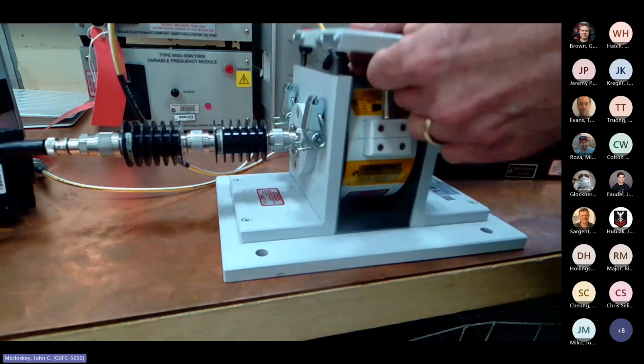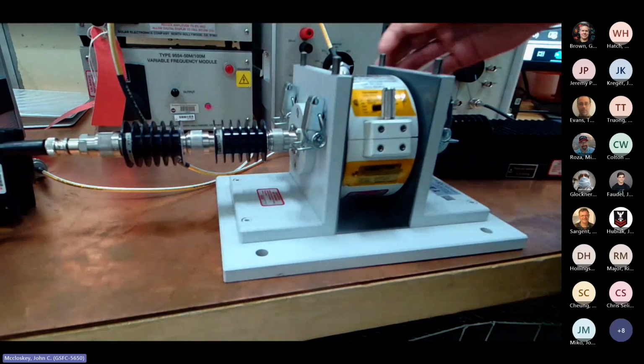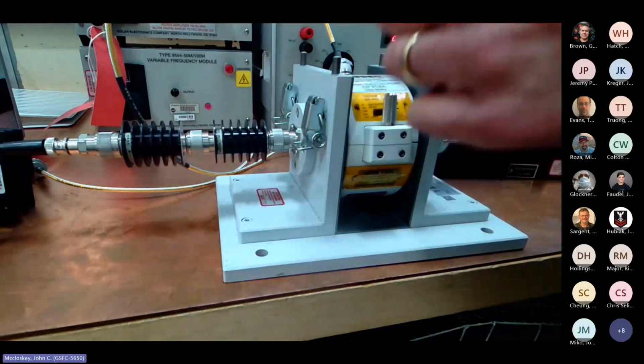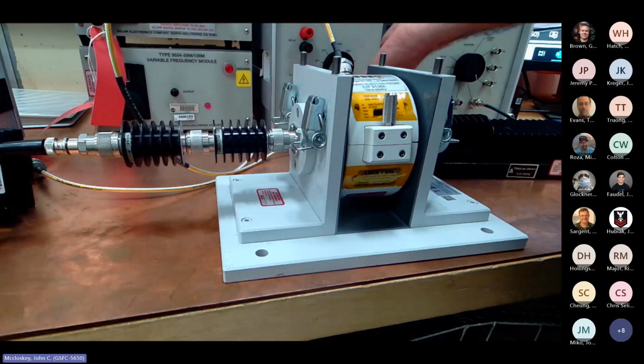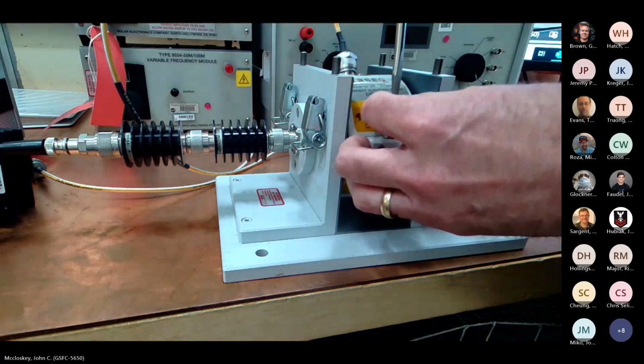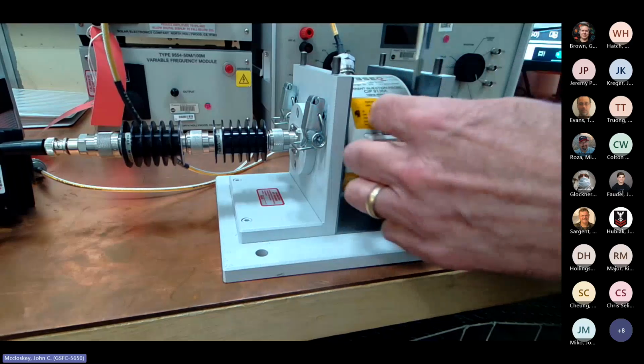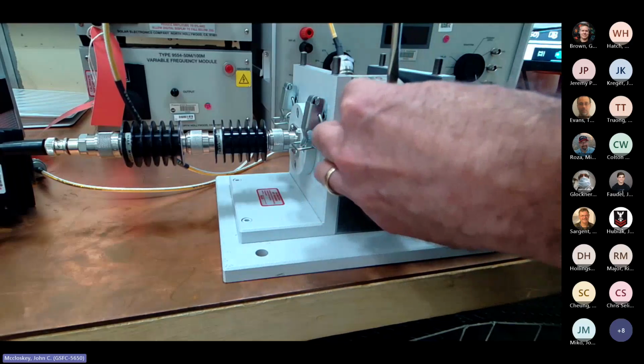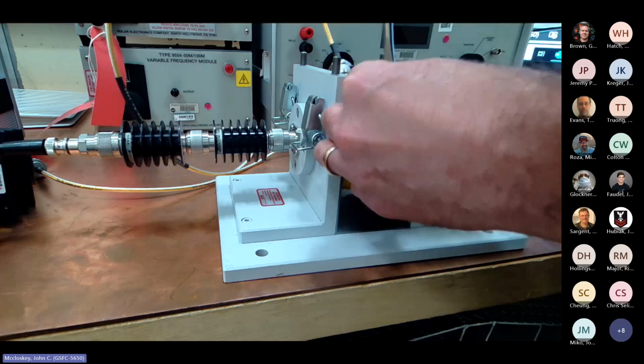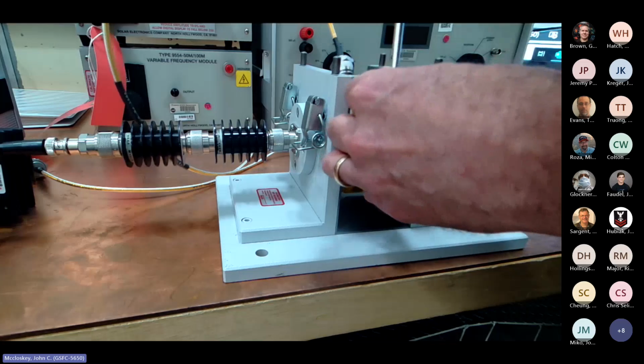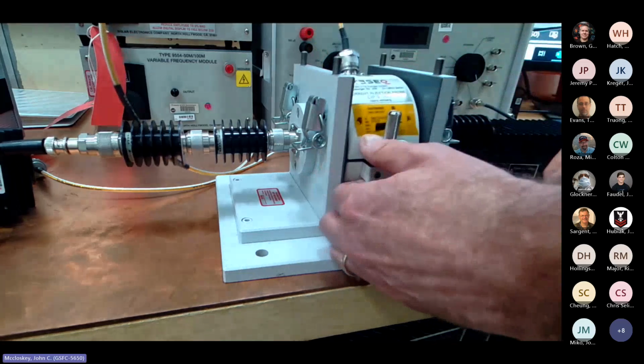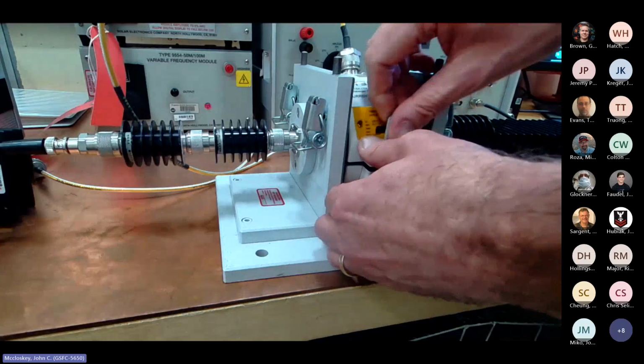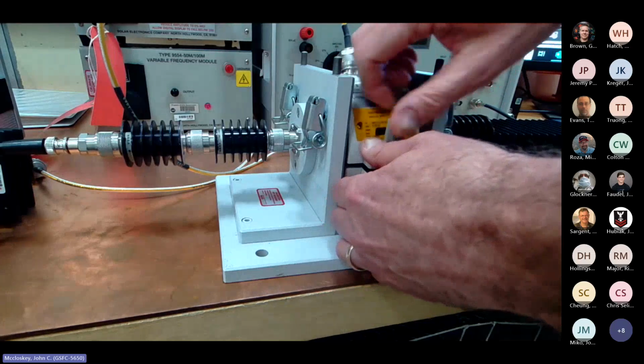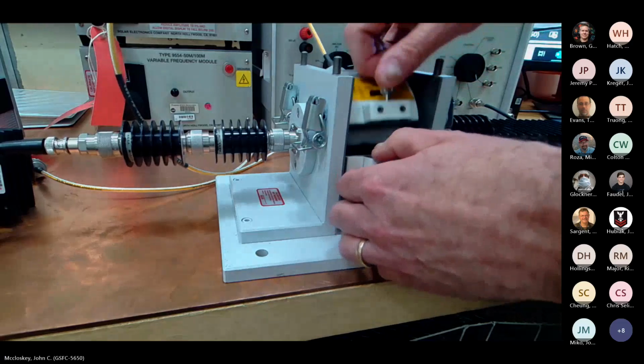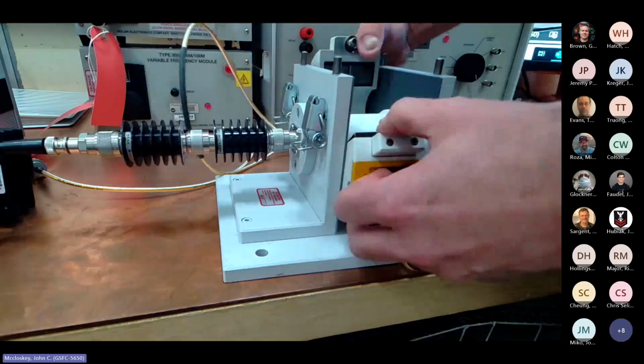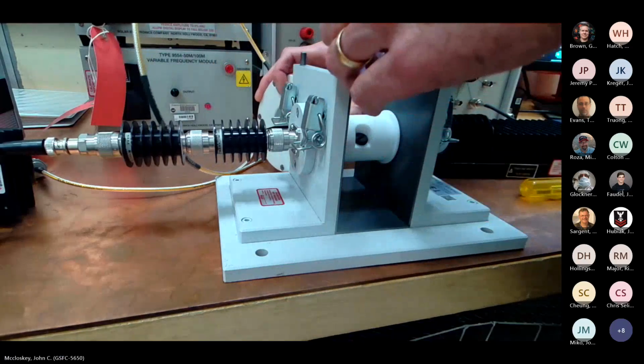These fixtures generally have a removable lid. Shut it down first - the output's disabled, but turning the power off is a good idea too. Don't do this sort of thing with a hot signal. That's one thing where the clicking is nice - it's annoying, but when you don't hear the click, the output is not enabled or energized. This particular probe has a screw on here, while others just have clasps that are much easier and quicker to remove, but this probe has a little better performance for what we're doing here, so much the better.